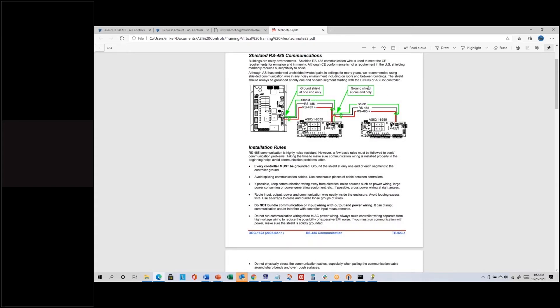Tech Note 23 was written 15 years ago but still contains good information we follow today. It covers recommendations for using shielded communication wire and how to terminate the shield. The method is a little different from how many people learned it. The common approach is to twist all shield wires together and ground them at the first or last controller in the daisy chain.